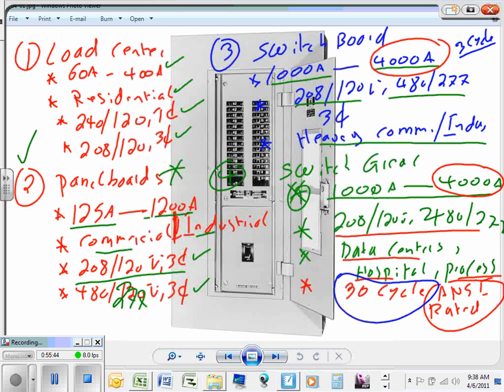The circuit breaker is no longer just a 100 amp circuit breaker. When you have switchgear or a switchboard, they don't just talk about a 100 amp circuit breaker. They talk about frame size. You're going to hear them talk about the frame size of the circuit breaker, meaning the physical, mechanical dimension of the 1000 amp, the trip size, the sensor size, and the setting size of the circuit breaker. So every circuit breaker has 3 sizes when it comes to switchgear and switchboards, unlike these, which have only one size, 15 amps. Before I go to this one, I just want to highlight the sizes in a second. Any questions, guys, about these?